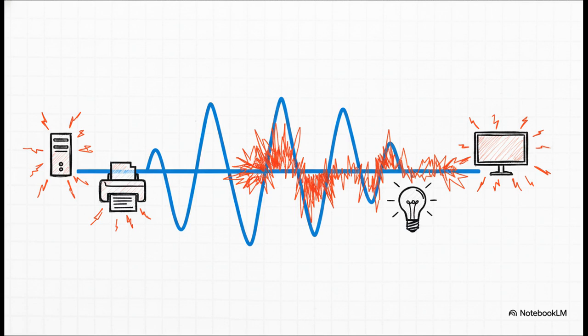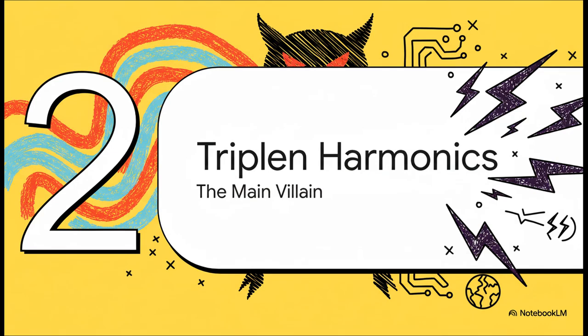Every single one of these devices, these nonlinear loads, takes that beautiful, clean sine wave, chops it all up, and spits this electrical noise right back into the building's wiring. But not all harmonics are created equal. There's one particular type that is, without a doubt, the main villain in our story: they're called triplen harmonics, and in our modern three-phase power systems, they are uniquely dangerous.